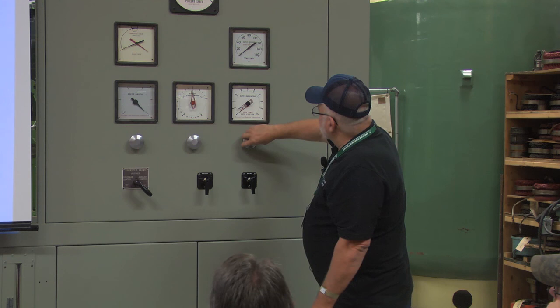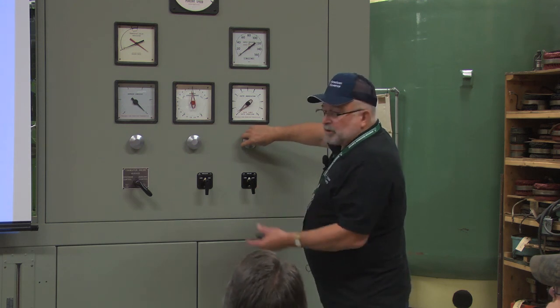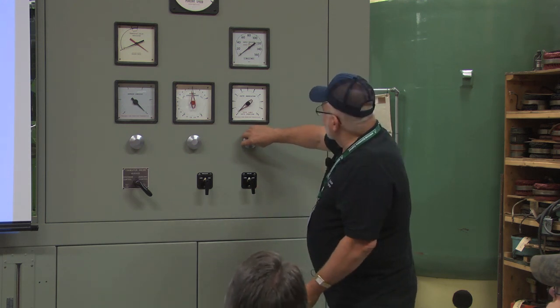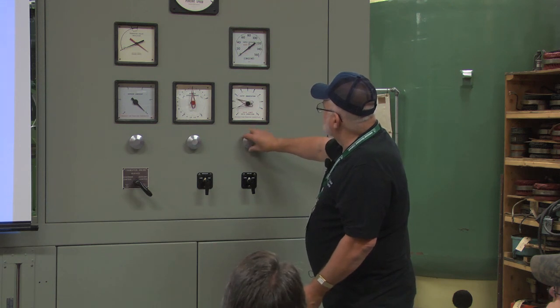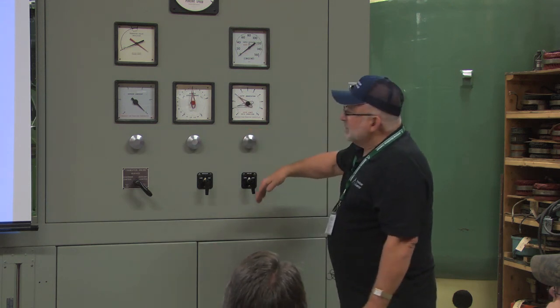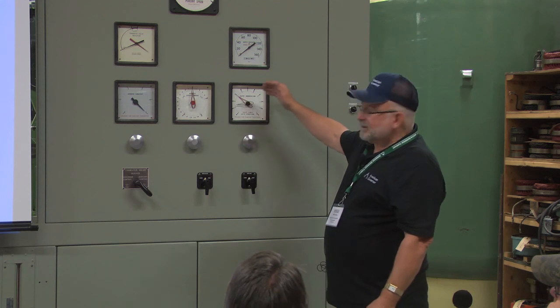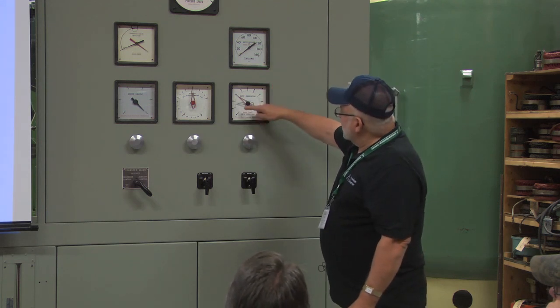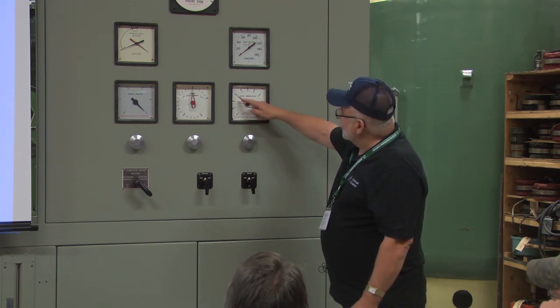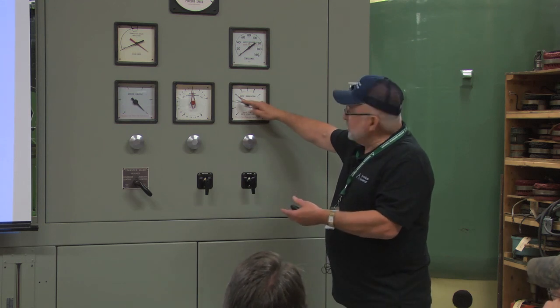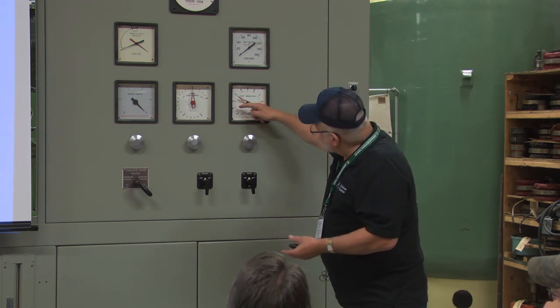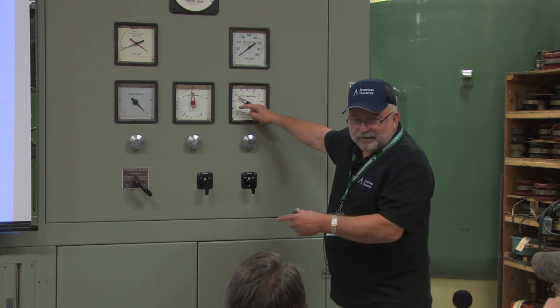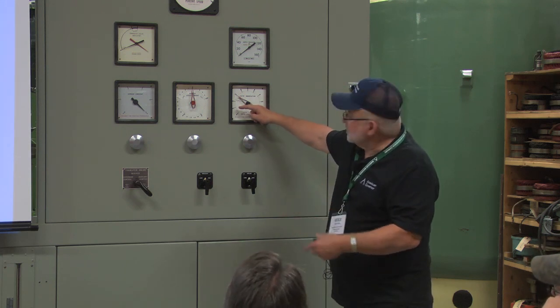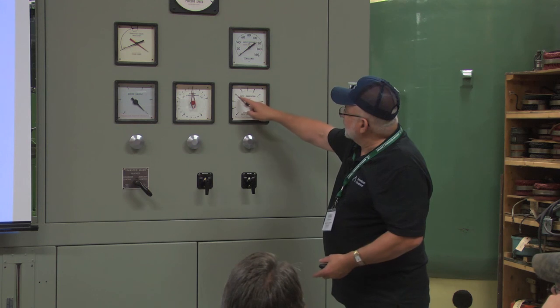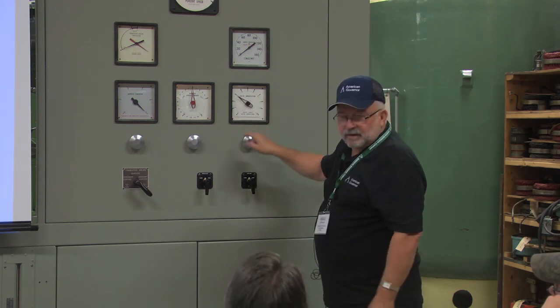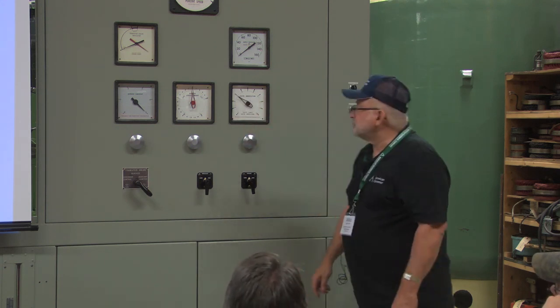So you're sitting here going, you hit the start button, you got your cooling water on, you're going to go. It goes. Now the speed starts coming up and everything. And then this hand's going up, all right? Now you're almost to rated speed. The governor grabs it, and this comes down to about 10 and sits there wherever that speed no load is. It sits there, and then when you parallel the unit, this goes out of the way. The limit goes out of the way.